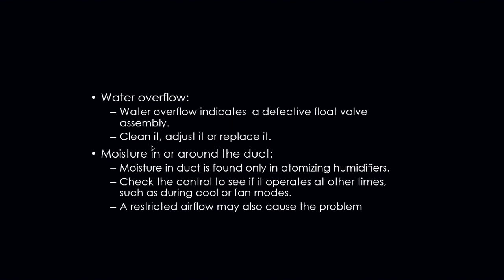Water overflow. The water overflow indicates a defective float valve inside there. When you walk up to a humidifier and you start seeing water dripping all over the place, probably you might have a bad float valve in there. That's no good, okay? Because remember, we have a reservoir. That reservoir is going to fill up with water. We've got to have something in there that's going to shut the water flow off so that we don't constantly dump water and spill it all over the place. Okay? Ways to get around that: we can take it out, clean it, adjust it if we have to. Some float valves are adjustable. And if that doesn't work, we simply replace it.